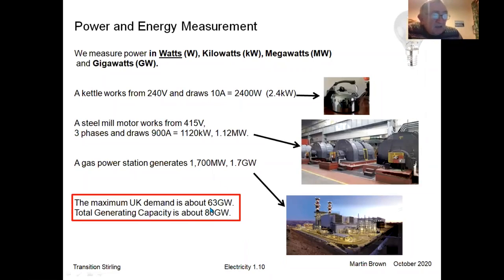The maximum demand in the UK, and I always think that's going to be on a cold, dark, cloudy January morning, where all the factories are switching on and everybody's still got their lights on and all the offices and everyone's got their heating running. Typical maximum load is about 63,000 megawatts, 63 gigawatts. So it's very important that the generating capacity always exceeds the maximum load, because at the moment anyway, it's very difficult to store electricity. It's one of the great challenges we have, finding a way of storing electricity. That's why we always have to have a little bit of reserve between 63 and 80. So that's very quickly, in a nutshell, how our power system works.